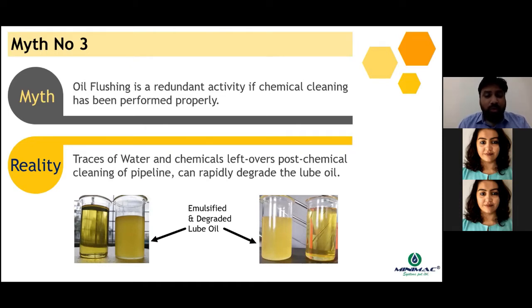This would lead to very hazardous situations where the oil might get emulsified with water, the oil might get degraded because of the chemicals in the chemical cleaning agents, and thereby at the very commissioning of your equipment, you would have a failure of your lube oil system because the lube oil has already got degraded. It has lost its lubrication properties. So there you might have to engage further equipment for purification and removal of the unwanted foreign material from your lubrication system. This would add to your further activities of the project commissioning if you have not done the flushing after the chemical cleaning activity.